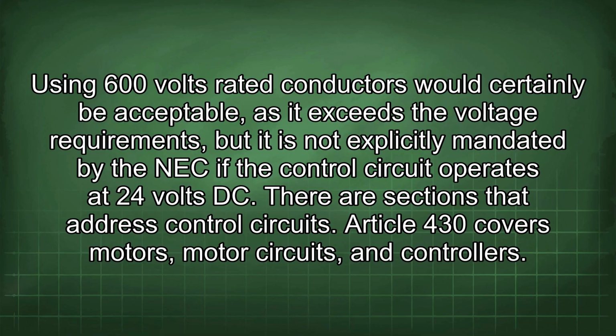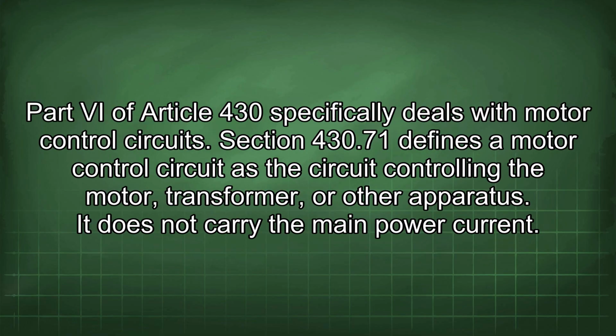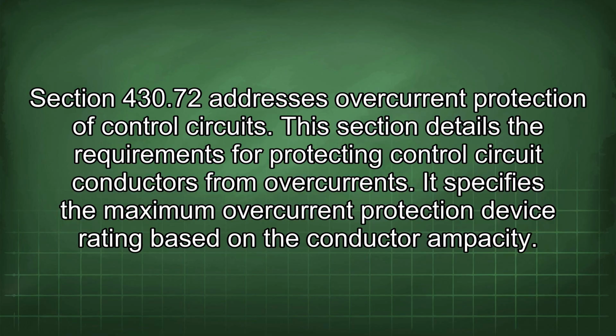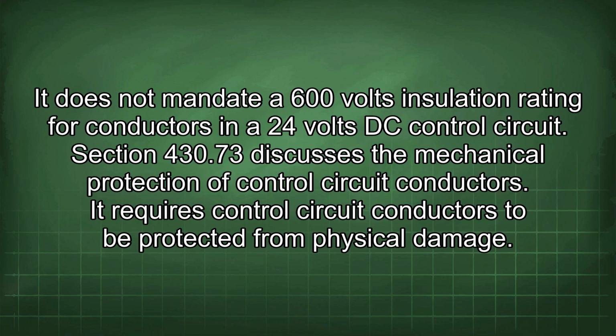There are sections that address control circuits. Article 430 covers motors, motor circuits, and controllers. Part VI of Article 430 specifically deals with motor control circuits. Section 430.71 defines a motor control circuit as the circuit controlling the motor, transformer, or other apparatus. It does not carry the main power current. Section 430.72 addresses overcurrent protection of control circuits. This section details the requirements for protecting control circuit conductors from overcurrents. It specifies the maximum overcurrent protection device rating based on the conductor ampacity. It does not mandate a 600 volt insulation rating for conductors in a 24 volt DC control circuit.